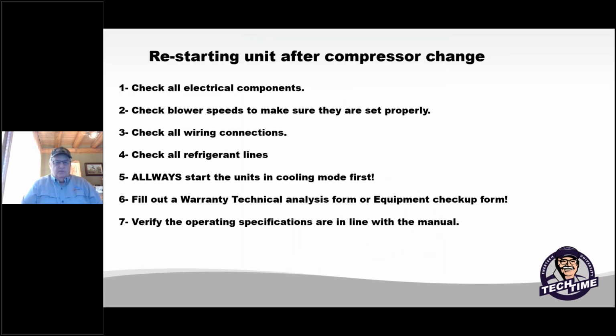When you're restarting the compressor after you've done all the change out, again, it doesn't hurt to double check your electrical components and check your wire tightness connections. If you have a forced air unit, make sure the blower speeds are set appropriately to the system design. Check your wires, look at your refrigerant lines again. You've been in there welding and moving things around, so make sure the capillary tubes aren't hitting any wires and nothing's rubbing.